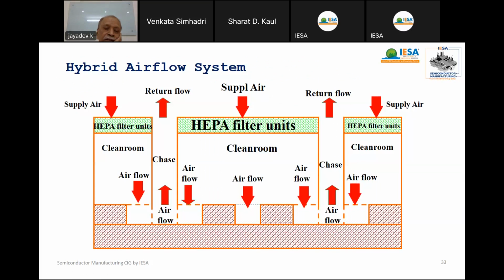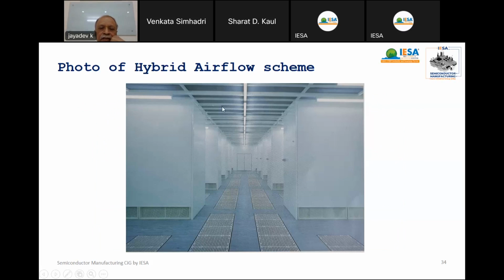So another method is hybrid. Mostly people may not use it, but suppose in a big clean room, we want to make only a small portion as ISO 5 or ISO 6 in an ISO 7 clean room. You can use perforated flooring in this portion where you need ISO 6, vertical laminar flow, and the balance return air can be taken back like this, vertical as well. See how it looks. From the ceiling, vertical air can go here wherever required, and return also goes all along the low level of the wall.